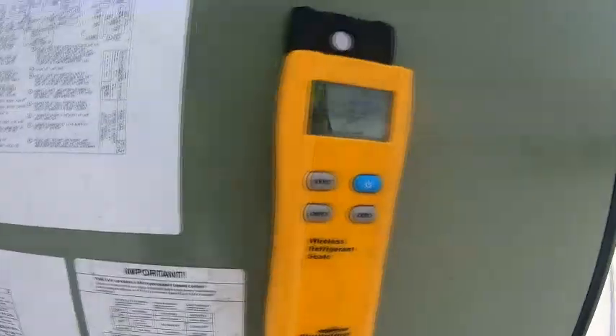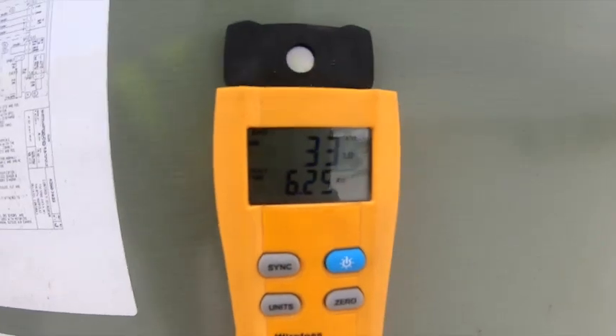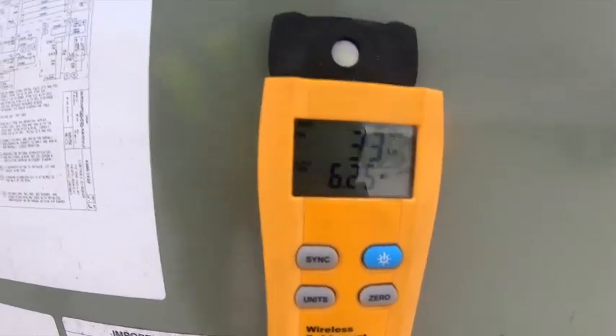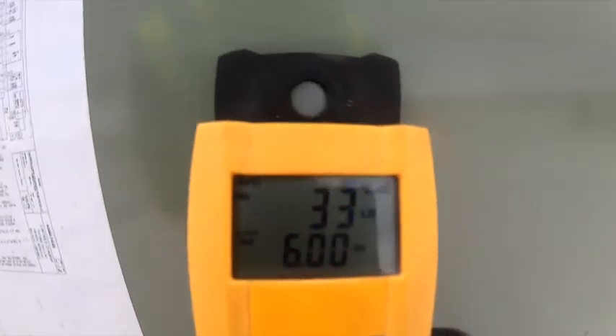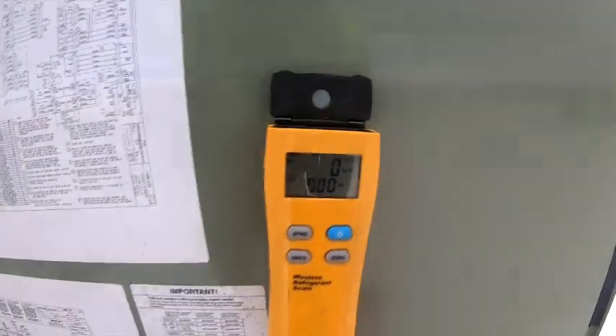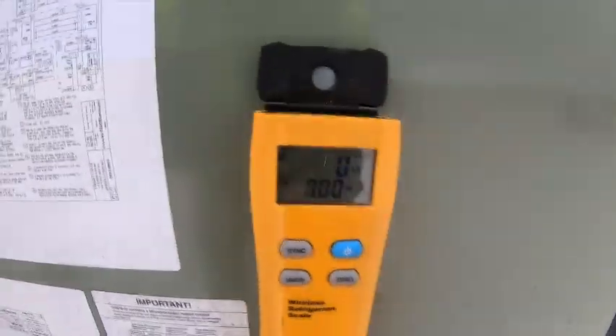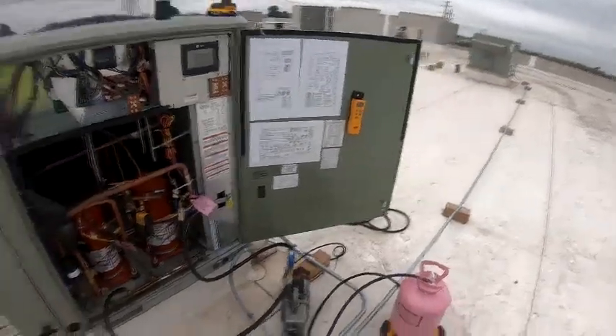So these 410A drums weigh about 9 pounds. That's a 25 pound drum. So 25 plus 9 is about 34 pounds. So 34 take away 9 gives me 25. But anyway, I'm just going to zero it out. So the tag said it put 6.2 pounds in there. So I'm going to put probably about 6.4, since those hoses are so big.